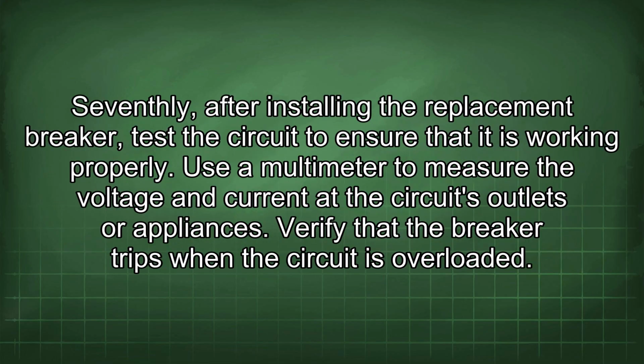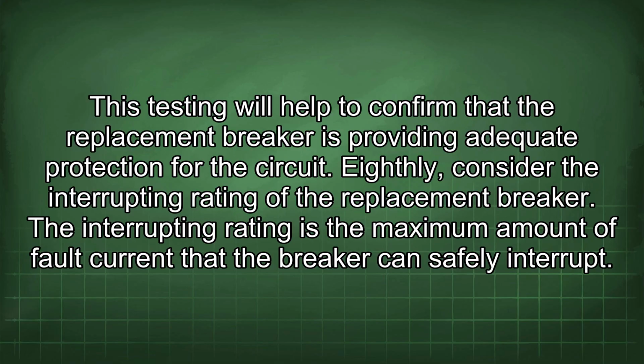Seventhly, after installing the replacement breaker, test the circuit to ensure that it is working properly. Use a multimeter to measure the voltage and current at the circuit's outlets or appliances. Verify that the breaker trips when the circuit is overloaded. This testing will help to confirm that the replacement breaker is providing adequate protection for the circuit.